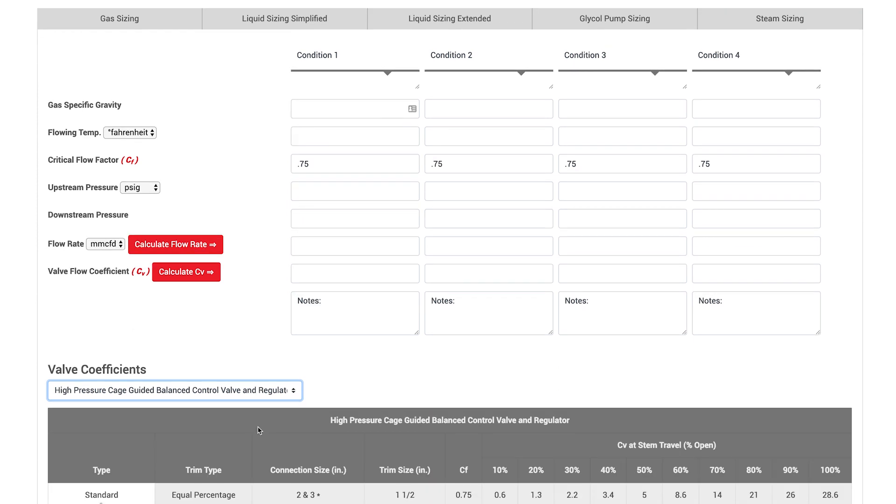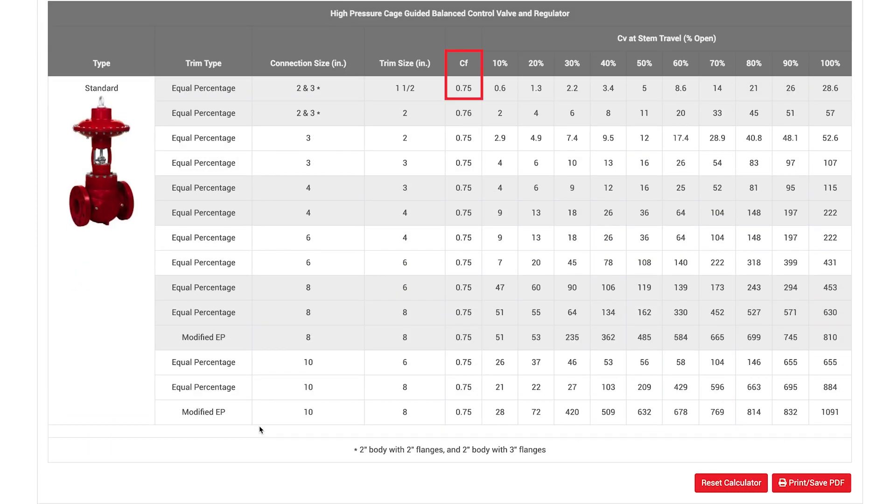Note that all globe-style control valves have a CF that stays consistent regardless of the stem travel, unlike the CV value which increases as the valve opens.